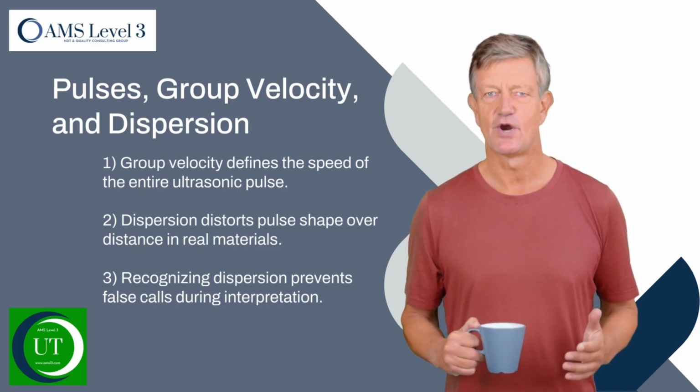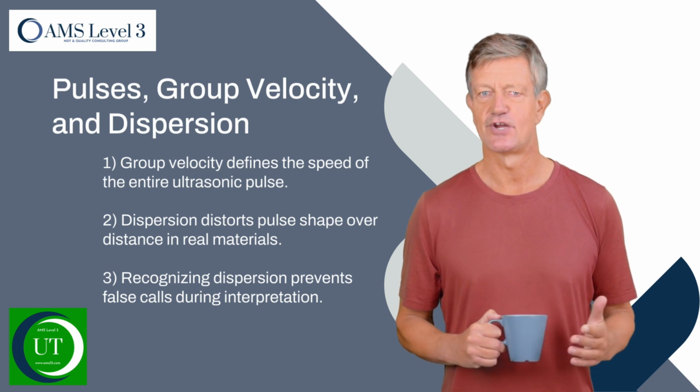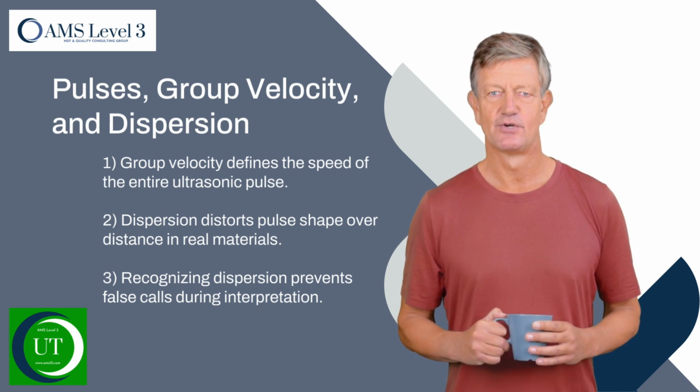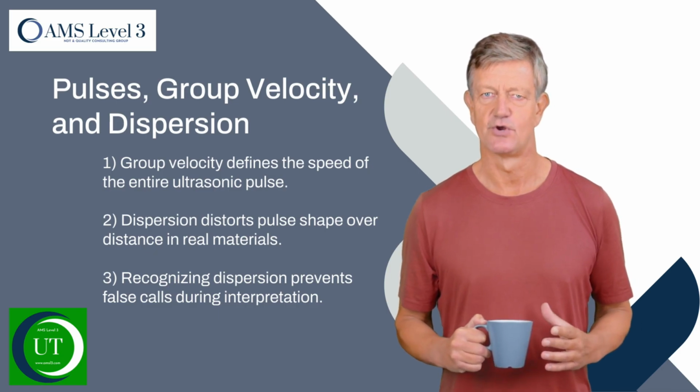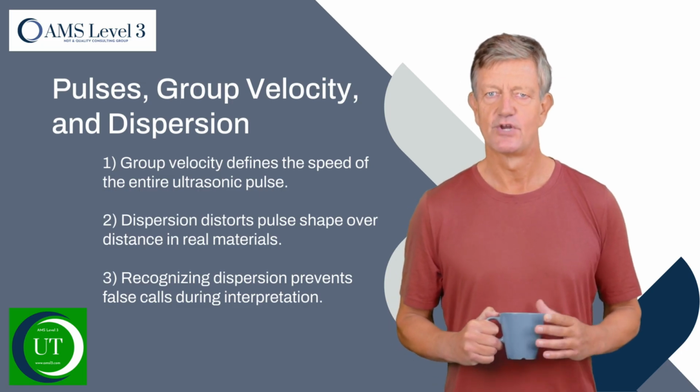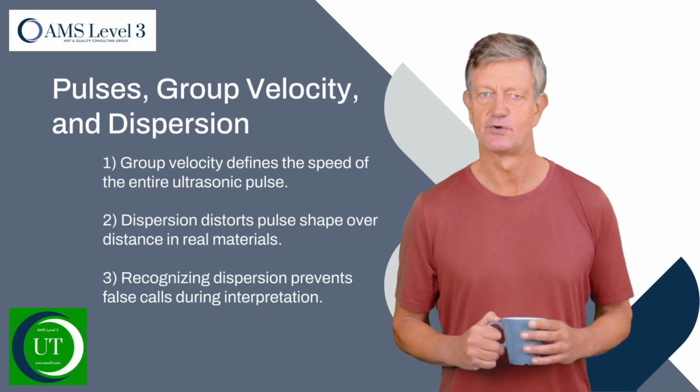I once saw a tech call a false indication because the signal stretched due to dispersion in a cast material. If he had understood wave behavior, he'd have caught it instantly. Remember, you can't correct what you don't recognize. And that recognition starts with grasping how real-world materials affect your pulse.